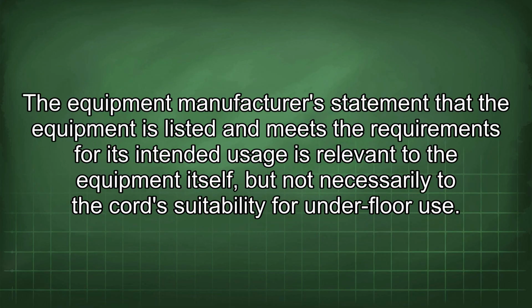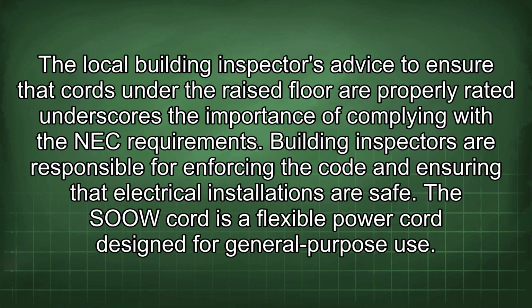The equipment manufacturer's statement that the equipment is listed and meets the requirements for its intended usage is relevant to the equipment itself, but not necessarily to the cord's suitability for underfloor use. The local building inspector's advice to ensure that cords under the raised floor are properly rated underscores the importance of complying with the NEC requirements. Building inspectors are responsible for enforcing the code and ensuring that electrical installations are safe.